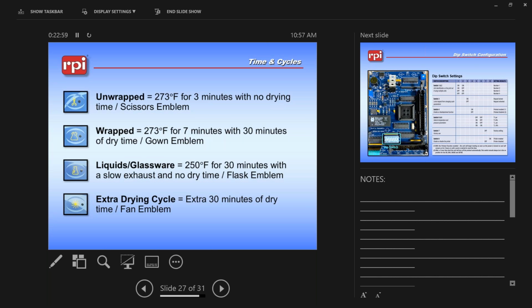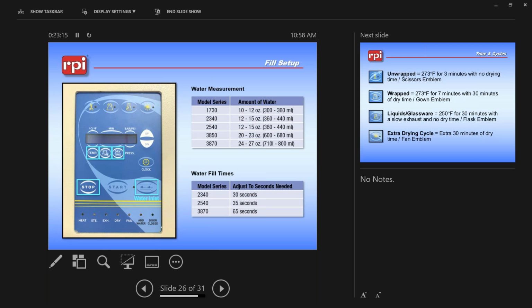Now on these units, there's your 4 standard setups: unwrapped, wrapped, liquids, glassware, and of course an extra drying cycle with the emblems to match for each. Now, going back one slide, at the right below your display, there's the temp, STE time, and dry time keys. These keys are used to adjust any cycle parameters that you want to. Of course, pressure is not one of them because pressure is just a correlation of temperature.